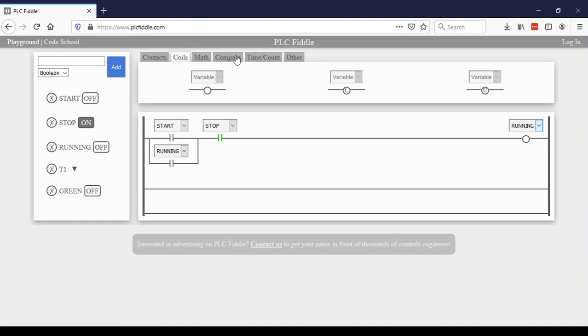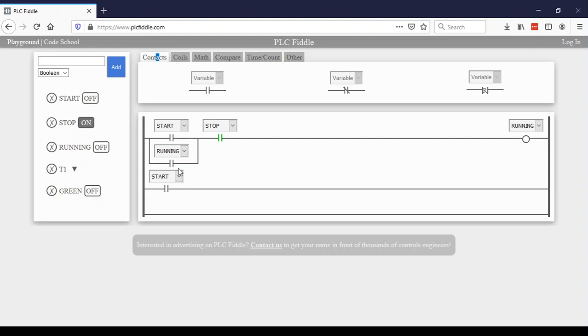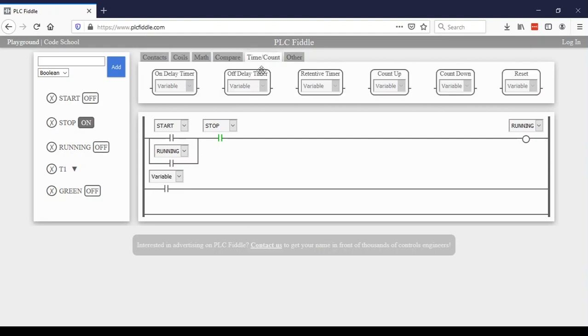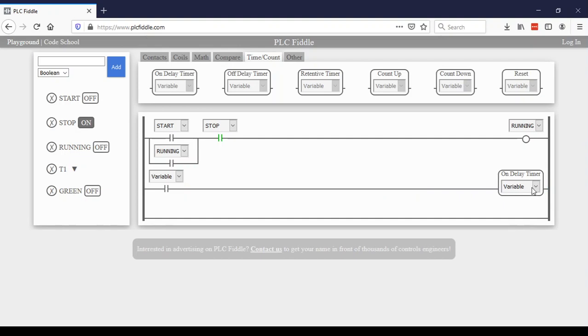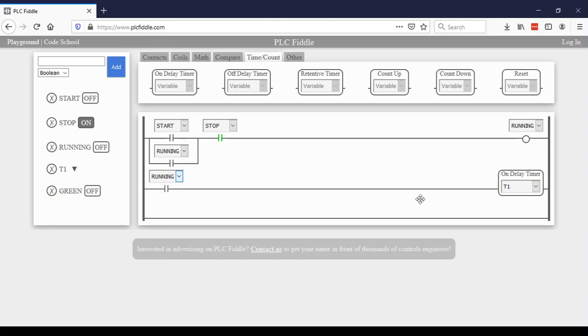My second rung, I'm going to work on the timer. So I'm going to insert another contact and a timer. I'm choosing to use a TON, is what we've been calling it, or a timer on delay timer as they are calling it. I'm going to make sure I have it set up to connect to T1 and I'm going to have this connect to running. So when running, start and run the T1 timer.